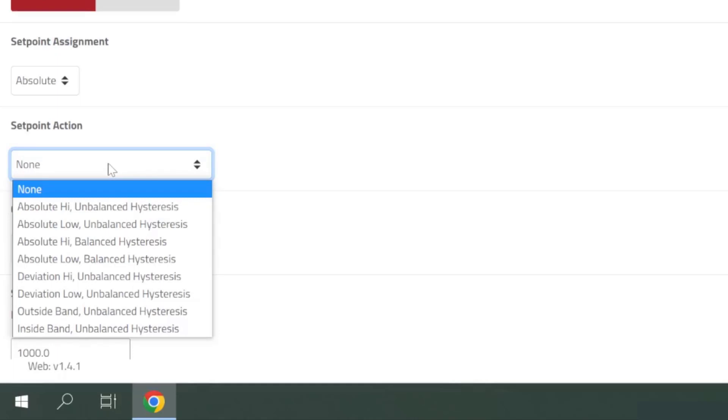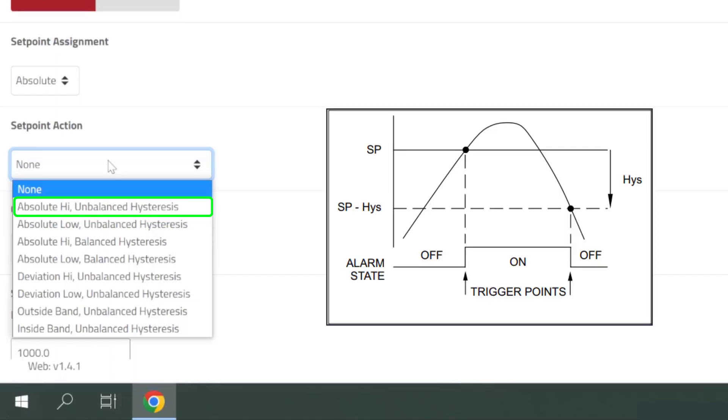You'll notice these selections have various hysteresis options, which can help to prevent the setpoint from bouncing rapidly between the active and inactive states, when the measured value is very close to the setpoint value. In this example, I'll be selecting Absolute High with unbalanced hysteresis, because I want to trigger the setpoint alarm when the measured flow value goes above the setpoint value, and I want it to stay triggered until the measured flow value goes well below the setpoint value.